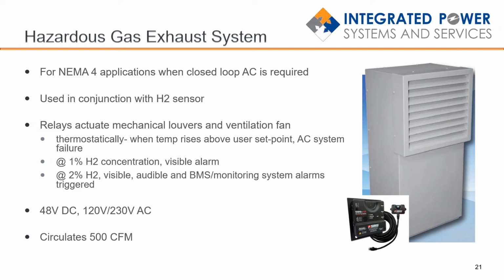And what we do is we have a hydrogen sensor that we wire in through some contacts, and then we have a dual purpose venting system which will actuate at 1% hydrogen concentrations and also sends up an alarm to the user. And at 2%, it sends out a second alarm. But at 1%, it's automatically going to start venting the enclosure and bringing in fresh air and exhausting all the air on the inside of the cabinet.